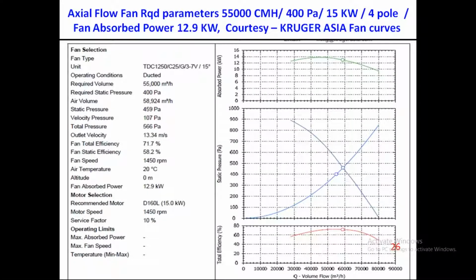Fan performance curve: if you have not taken it from the industry, as an energy auditor you go to the fan performance curve. Whatever the industry has bought the fan, don't buy this fan as a commodity, buy the fan performance curve. This will show the absorbed power of the fan in the top graph, and the static pressure, the meeting point of the static pressure, maximizing the flow and the pressure for the given kilowatt. This is the best efficiency point of the given fan.